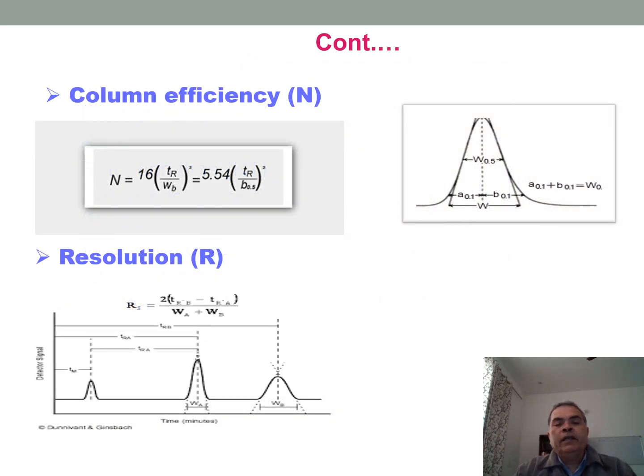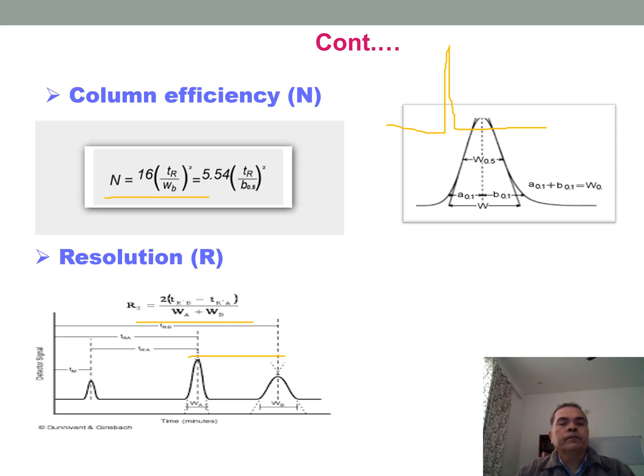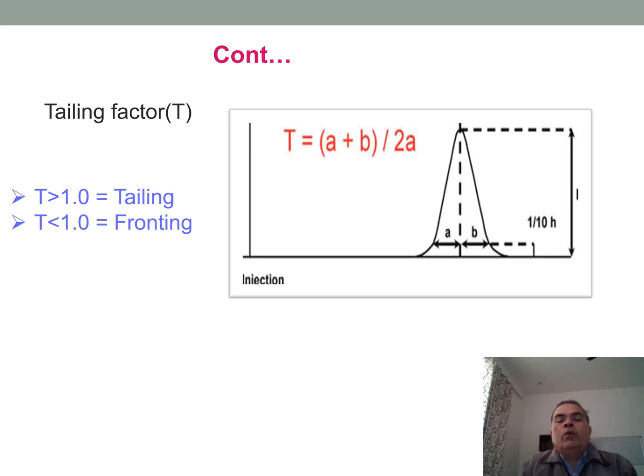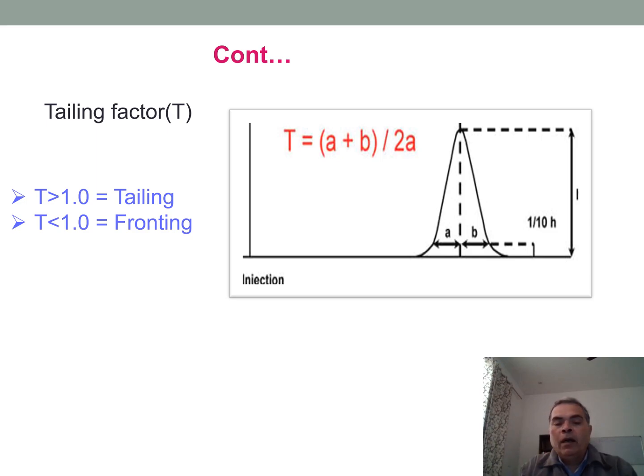Column efficiency describes the narrowness of the peak and is calculated by a specific formula. Resolution describes the separation between two peaks and is calculated by its formula. Tailing factor is calculated by the formula (a + b) / 2a. When the tailing factor is greater than 1, tailing occurs; when less than 1, fronting occurs.